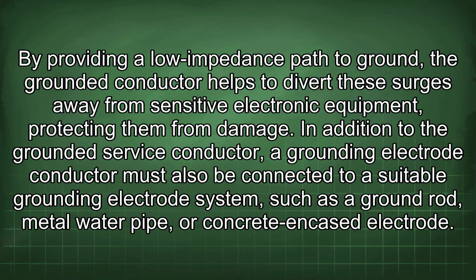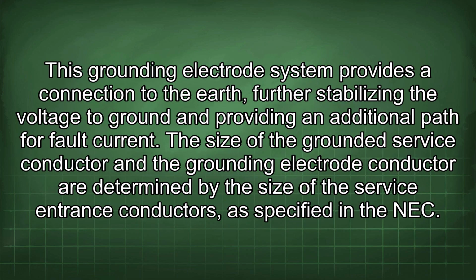In addition to the grounded service conductor, a grounding electrode conductor must also be connected to a suitable grounding electrode system, such as a ground rod, metal water pipe, or concrete encased electrode. This grounding electrode system provides a connection to the earth, further stabilizing the voltage to ground and providing an additional path for fault current. The size of the grounded service conductor and the grounding electrode conductor are determined by the size of the service entrance conductors, as specified in the NEC.